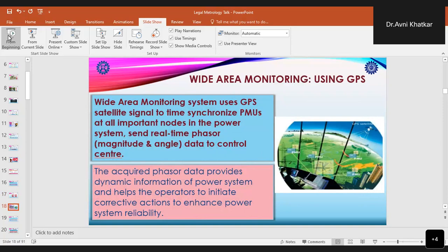Now, when we talk about the smart grid, in these smart grids, wide area monitoring systems, that is WAMS, play a crucial role, by capturing the measurements in the power grid over a wide area and across the traditional control boundaries, and then using these measurements to improve the grid stability and events through wide area situational awareness and advanced analysis. And these wide area monitoring systems use GPS satellite signals to time synchronize all the PMUs which are placed at all the important nodes in the power system.